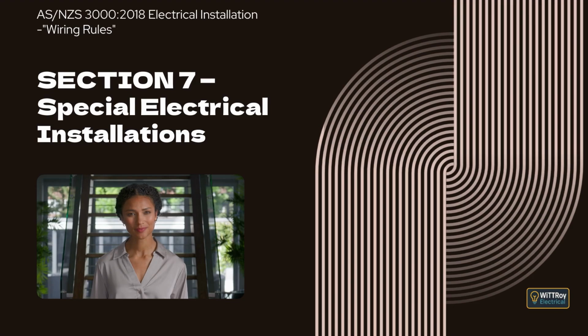Clause 7.3.3.1 Basic protection and fault protection. This clause explains that all necessary connections for basic and fault protection, including the MEN connection, must remain intact when supply is available from the electricity generation system. The intent is to ensure that protective measures continue to operate correctly regardless of whether power is coming from the network or the generator. Clause 7.3.4 Isolation. This clause introduces the isolation requirements for electricity generation systems so that equipment can be safely disconnected when required.